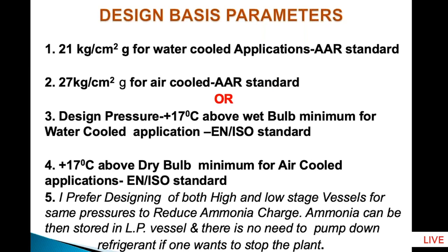The ideal alternative as per European standards is to consider design pressure at 17 degrees above minimum wet bulb temperature for water cooled application, and 17 degrees centigrade above dry bulb temperature for air cooled application. So for water cooled, go by the water temperature, that is wet bulb, plus 17 degrees centigrade, and for air cooled applications, take your city's maximum dry bulb temperature, add 17 degrees to that and consider it the design reference.